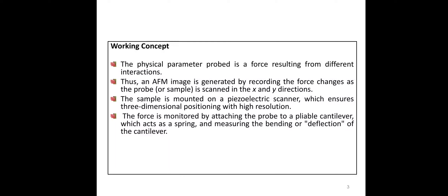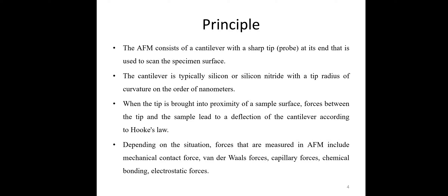The force is monitored by attaching the probe to a flexible cantilever which acts as a spring. Measuring the bending or deflection of the cantilever results in recording the image using a photodetector. The cantilever is made up of silicon or silicon nitride material, and the tip radius is a few nanometers — that is what we call nanoscale.